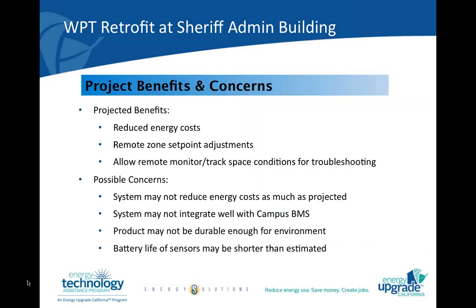And the benefits: reduced energy cost, remote set point adjustments. As Elizabeth mentioned earlier, there are some great things about this night setback. We can make changes if we decide to change our temperature settings throughout the year. Currently, if we say that summer setting is 76 or 78 degrees and the winter setting is 68 or 70 degrees, and maybe have a fall and a spring setting, it can take half a day or so for somebody to walk around and change those settings on the pneumatic stats. With this, we can do it for one spot, takes a minute, or maybe it's just part of a program sequence, it just happens automatically. So there's definitely some time savings there, as well as some remote information that's available through the network. In case a trouble call comes in, somebody doesn't have to walk over there with a temperature probe. They can read it from a remote location.